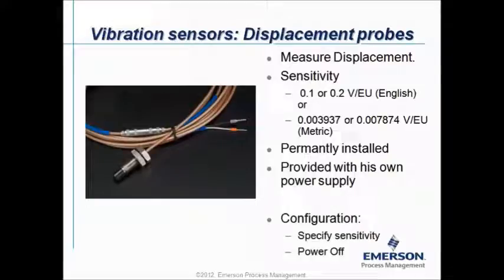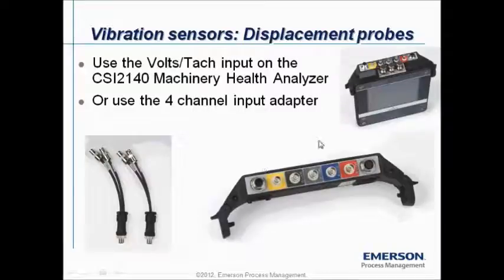The second kind of commonly used probe is called a displacement probe. It measures displacement. Very common on the market are two kinds of sensitivities, 0.1 or 0.2 volts per engineering unit in English systems. Those kinds of sensors are normally permanently installed, and they have their own power supply. So in the configuration you have to specify the sensitivity, and normally you have to disable the power. On the analyzer you have to consider it as a volt signal, and there is one input on the analyzer for a volt signal, this one here. So if you connect it to this one, you can measure 1 volt signal. If you're working with a splitter like this, you can go to 2 volt signals. If you're using the 4-channel input adapter, the other side of the adapter is for 4 volt signals.